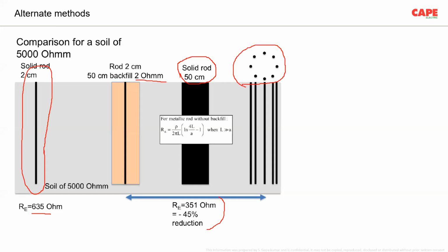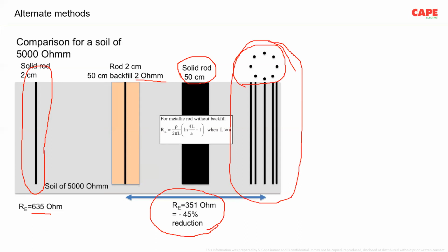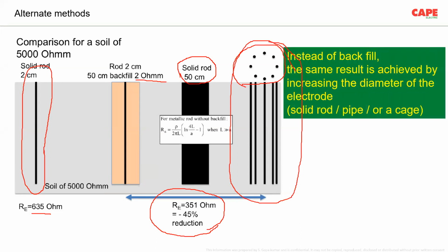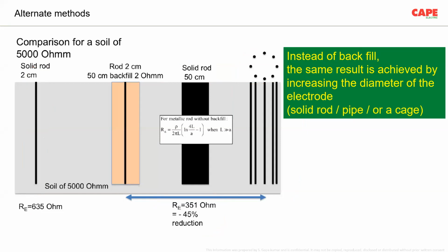the results are the same. It also means that instead of filling up this area with the earth enhancing compound, if you put a 100 mm pipe, or if you put a cage, something like this, a cage of 100 mm, the result is going to be the same, because it is basically improving the area. So instead of backfill compound, the same result is achieved by increasing the diameter of the electrode, something like this. In this picture where I am moving the cursor, the virtual diameter is increased by the earth enhancing compound. In the second case, the physical dimension of the pipe itself is equal to a large area. In the third case, a cage is made. So in all three cases, the result is the same.